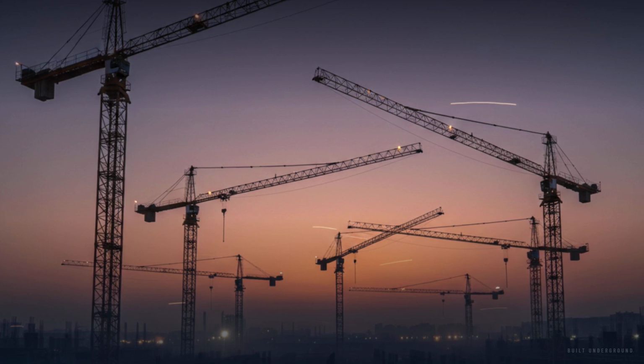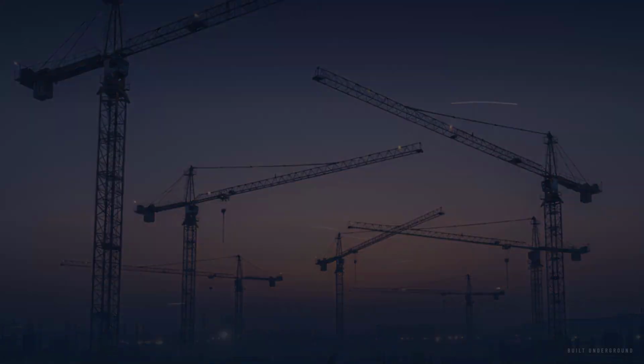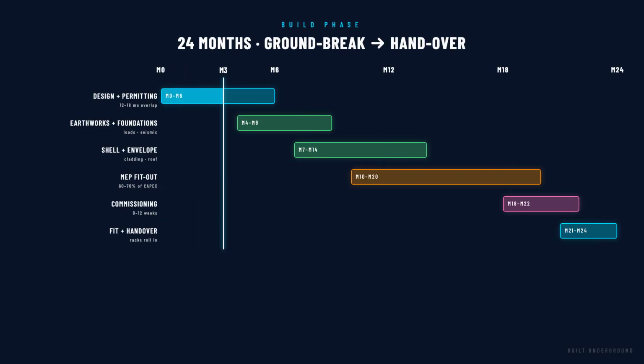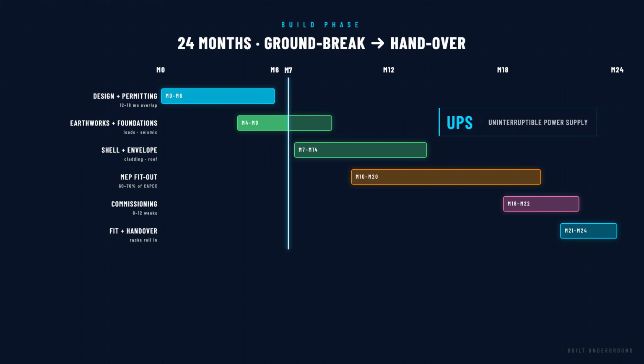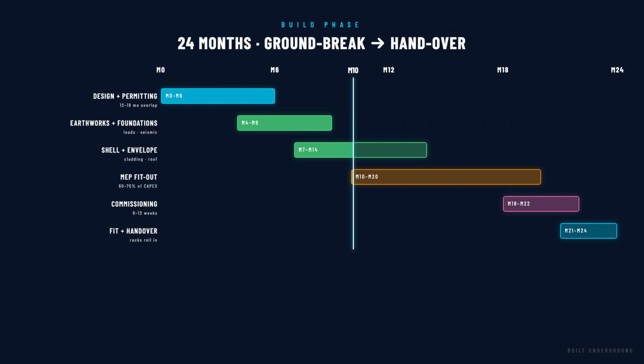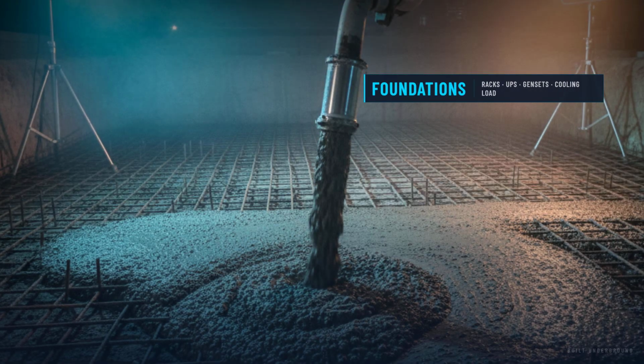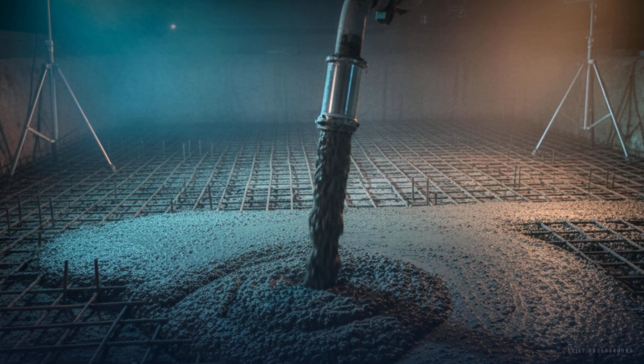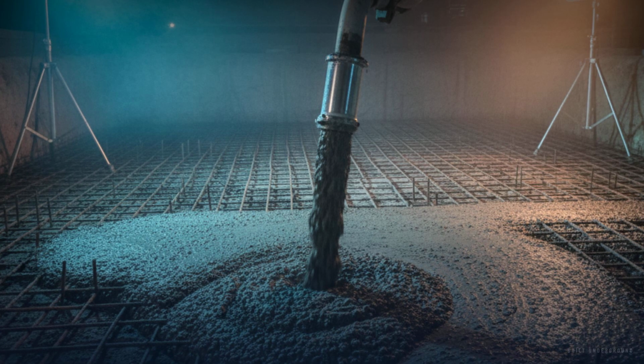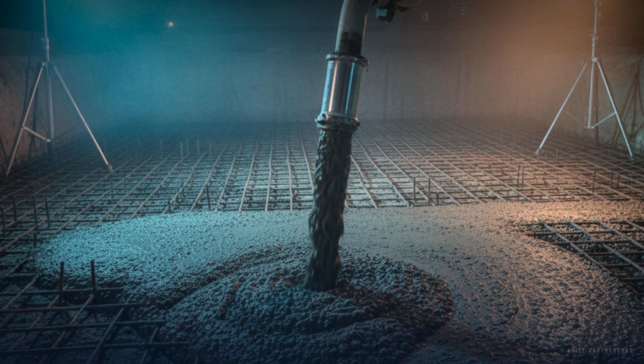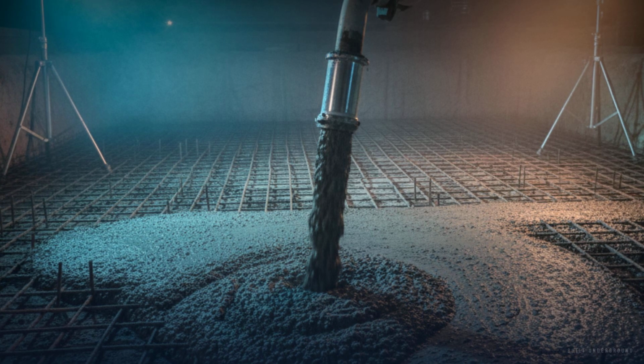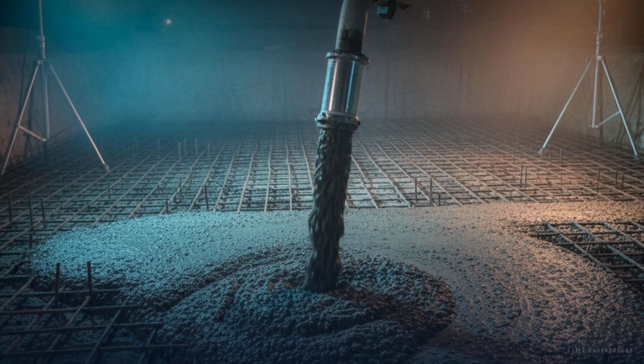phases. Foundations and structure come first. These buildings carry enormous loads. Server racks, UPS batteries, generators, and cooling equipment add up fast. The structural design has to account for all of it, plus seismic requirements depending on location. Then comes the envelope: walls, roof, weatherproofing. Data centers are typically clad in insulated metal panels. The building needs to be airtight and thermally efficient because controlling the internal environment is everything.